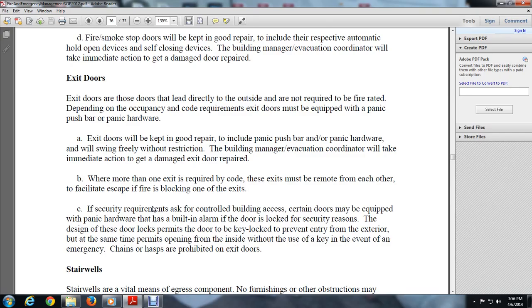Exit doors are doors that lead directly outside and are not required to be fire rated. Depending on occupancy code requirements, exit doors must be equipped with a panic push bar or panic hardware. Exit doors will be kept in good repair, and the panic push bar and panic hardware will swing freely without restriction. The building manager or evacuation coordinator will take immediate action to get a damaged exit door repaired. When more than one exit is required by the code, the exits must be remote from each other to facilitate escape from a fire blocking one of the exits.